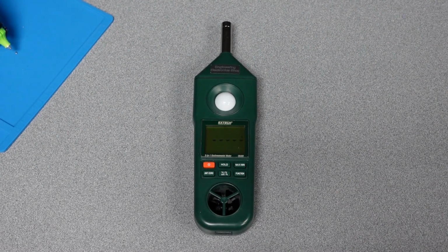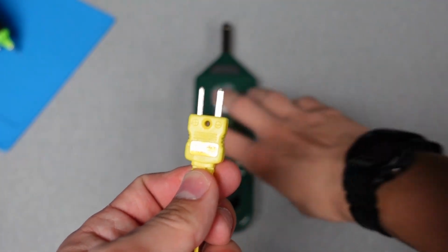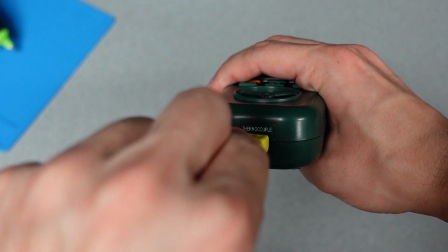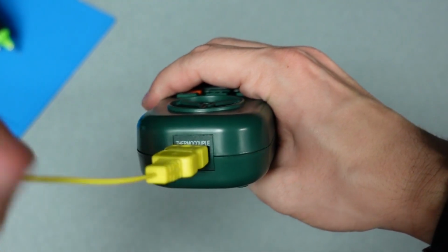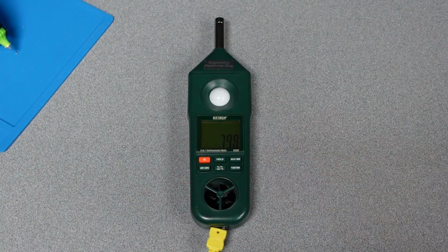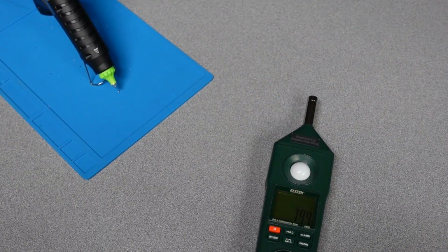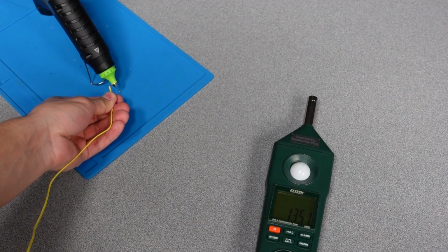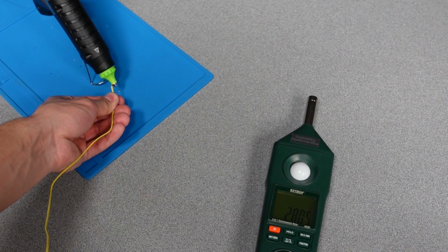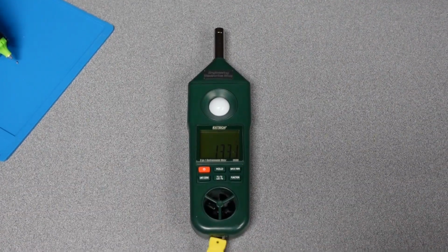Pressing the function button again, the meter will measure temperature once more. This time it will only measure temperature with the thermocouple, so insert the Type K thermocouple and ensure that the ground and positive markings on the thermocouple match with those on the meter. The thermocouple allows you to measure exactly at the point at the end of the thermocouple. The measurements made with the thermocouple are much more accurate and have a much larger range than those done with the internal sensor. You may see the manual for more details.